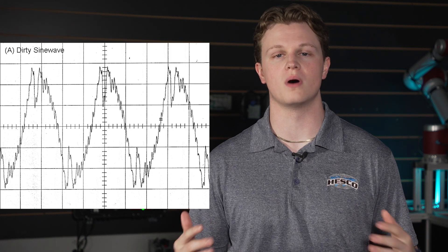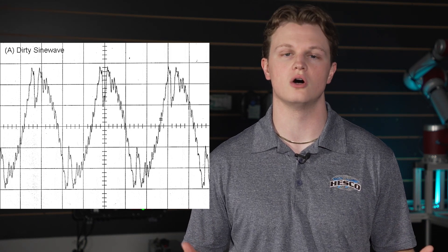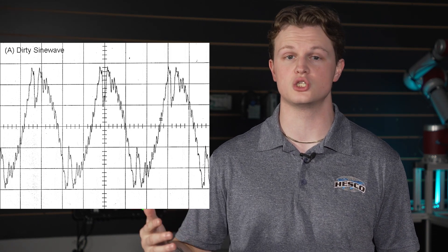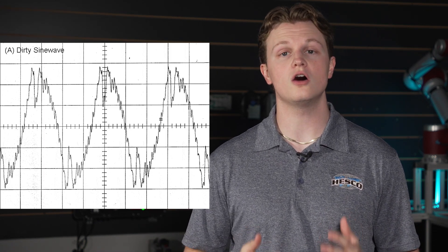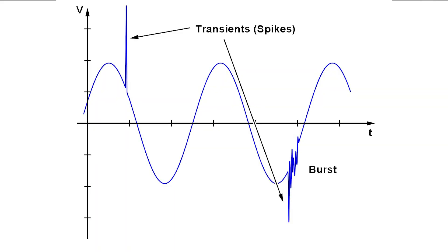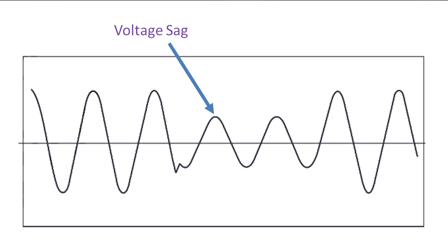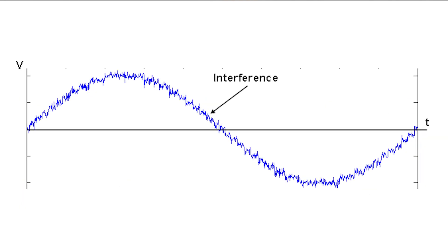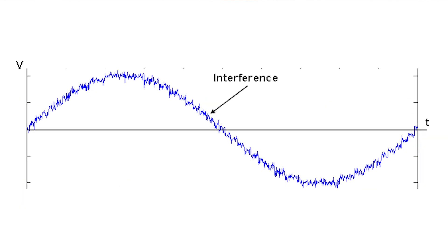Dirty power is characterized by a distorted sine wave with high total harmonic distortion, also known as THD, often exceeding 10% or more. It fluctuates in voltage and frequency, leading to voltage spikes, sags, and significant electrical noise.